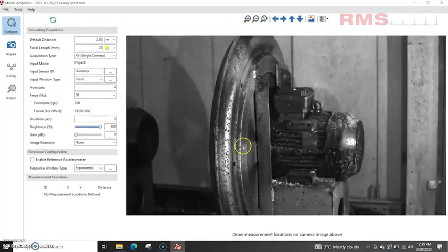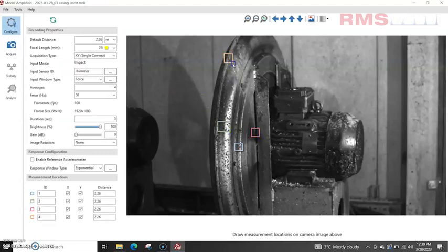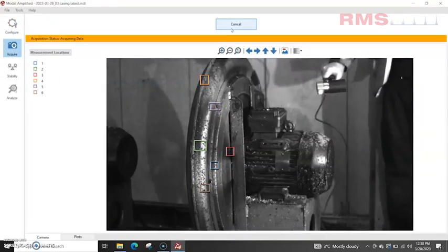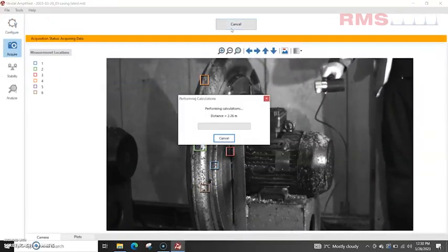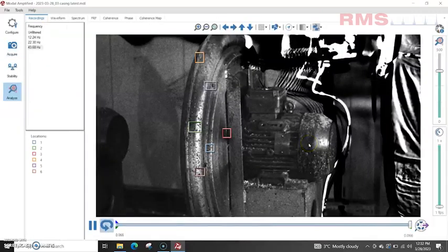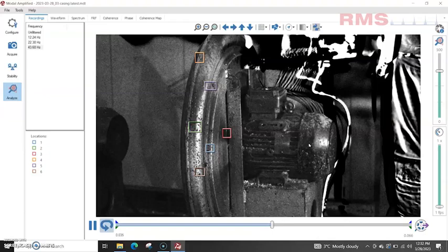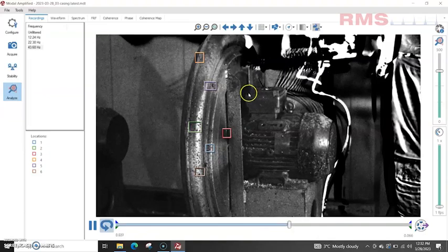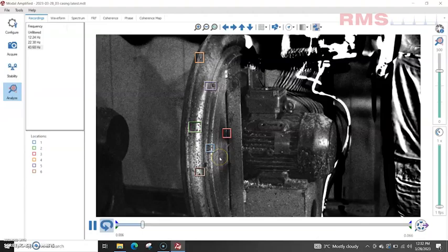So then I focused back onto the actual volute where the motion we'd seen in the MA and the previous modal test, and did some more detailed bump testing there. And we actually got, you can see here, we got some nice flexing of that casing, sort of top to bottom.